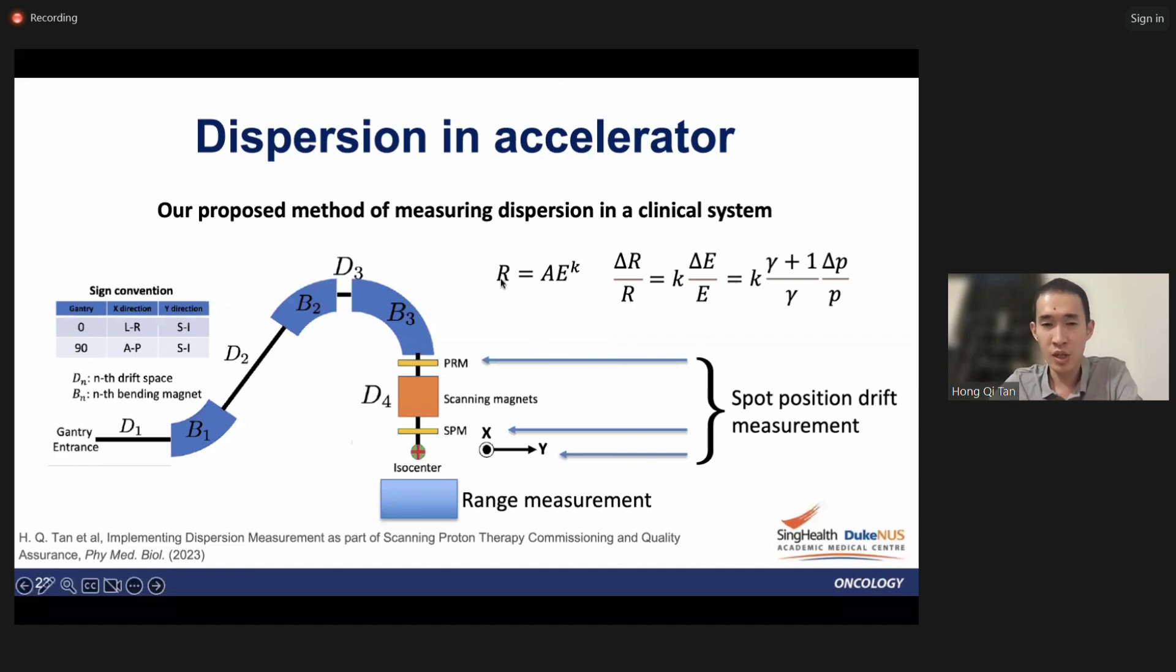In proton therapy, the range of the proton can be related to the energy using the Bragg-Kleeman relationship. If we do some simple algebra, differentiation and so on, you'll notice that delta R can be related to delta P over P. This means that if there's a momentum error in the extracted proton beam, it will translate to a range error. Using this knowledge, if we can measure the range error throughout the spill, we will have a way to measure the momentum errors.